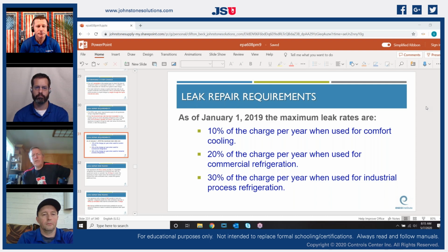But by establishing good, clear records and by using proper practices, like I said, of removing the refrigerant and putting it back into the liquid line before you leave the job. So we actually had a system where gauges going on and off were vital. We put them on when the system was not running because we didn't want to dry start one in case there wasn't anything in it. Then we took them off in the proper sequence.